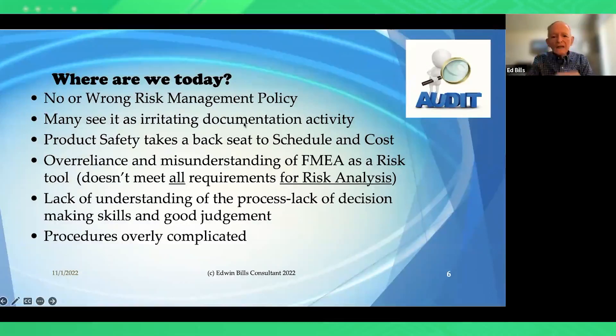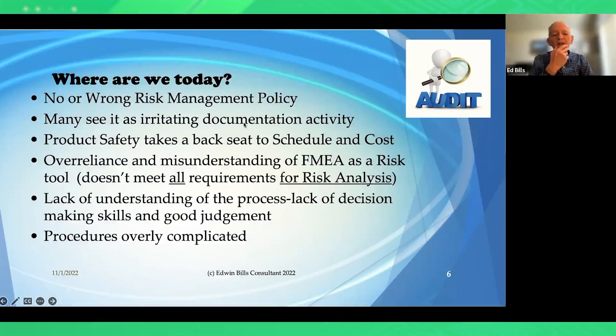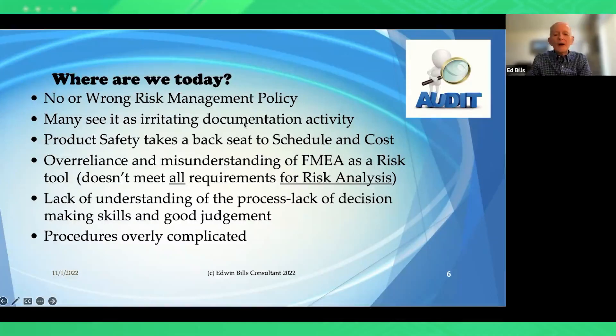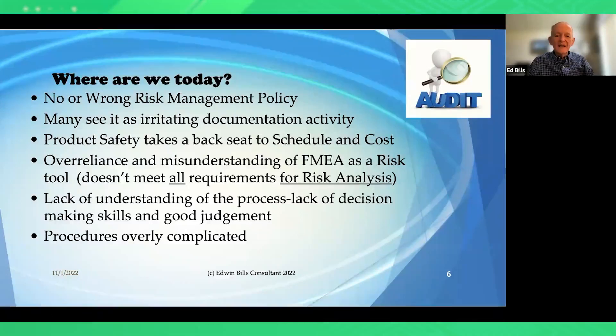A question came in: what are the key clauses of ISO 14971 for contract design houses who are not the legal manufacturer? Do they need a risk policy? Yes, they do, because they are responsible for design risk activities, which are based upon the risk management policy. Contract design houses need to understand the risk management process, because the outputs of risk management are design inputs — and that is exactly where a contract design house starts: developing design inputs.